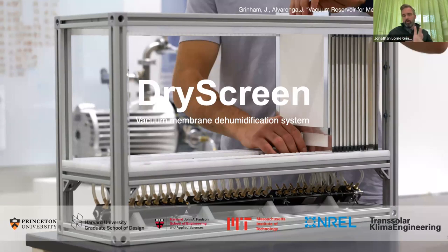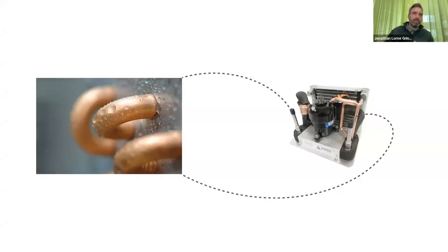How do we take care of that other 33% of our emissions related to cooling by dehumidifying without a typical vapor compression cycle or costly liquid desiccants? And DryScreen is a vacuum membrane dehumidification system that I'll explain in a second. But a typical vapor compression system inherently dehumidifies because as we pass air across the coils of that system on the evaporator side, we're going to have water condensate because we're driving it down below the dew point.